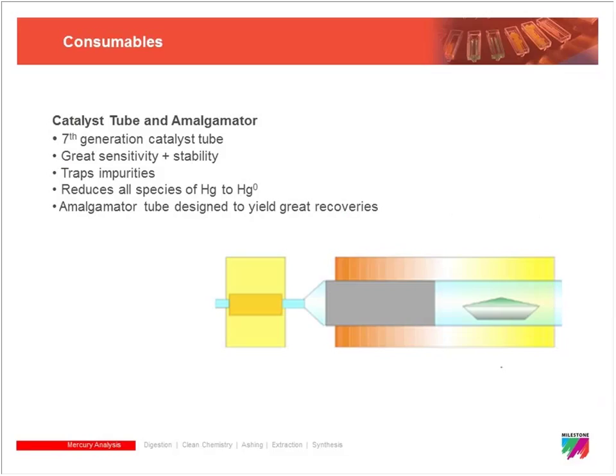So the catalyst and the amalgamator form the heart of the system, as I mentioned earlier. Currently we're on our 7th generation catalyst tube. So we've been able to develop a very stable and reliable catalyst that is capable of producing some very reproducible data. Again, just to recap, it will trap all the impurities and convert all the mercury species to elemental. It's then passed through to the amalgamator, which collects all the mercury and then releases it all simultaneously into the detector cell so that you can analyze all the mercury contained in your sample all at once.